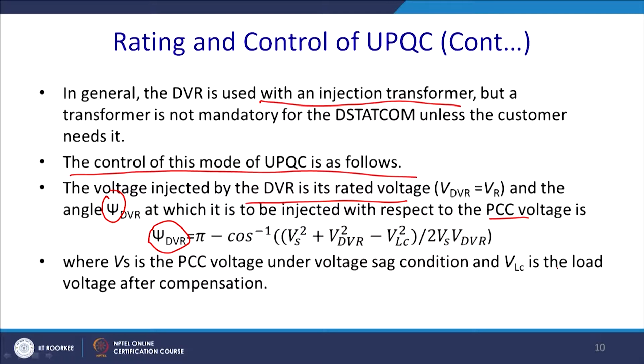The voltage injected by the DVR is the rated voltage, V_DVR, and the phase angle psi_DVR, at which it is to be injected with respect to the PCC voltage, is psi_DVR = pi minus cos inverse of (Vs squared plus V_DVR squared minus VL squared) by 2 Vs V_DVR. So, from there you get the optimal angle psi_DVR, the phase in which the DVR is to be injected, where Vs is the supply voltage under sag or swell condition and VL is the load voltage after compensation. So, ultimately this is the injected DVR voltage.